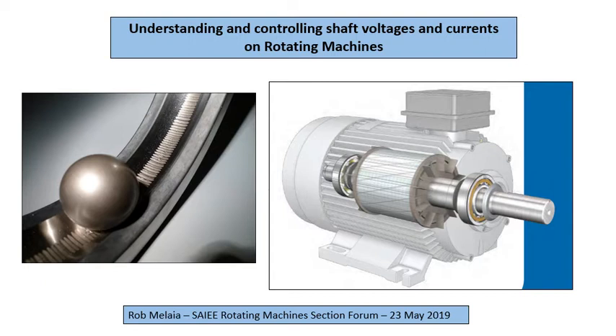That, courtesy of ABB, is typical fluting damage of a rolling element deep groove ball bearing. And there's the current. That should be smooth. And this is just showing the typical construction. There's your bearings, and Steon showed you where your currents flow. They either flow circulating in the frame, or they flow common mode, where it's the same polarity to Earth.